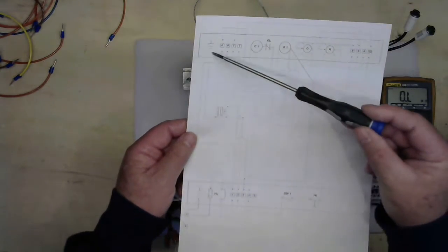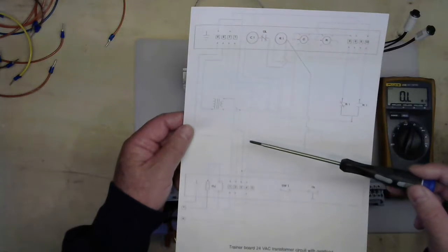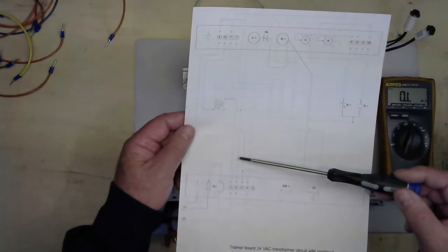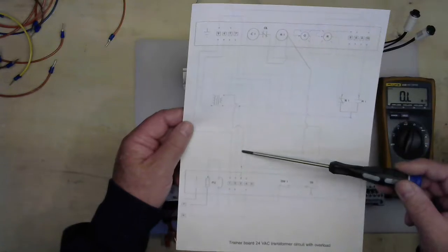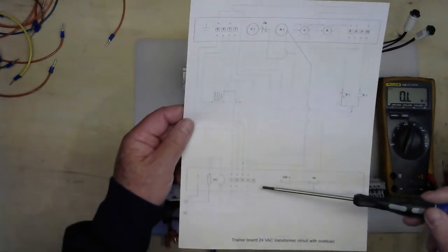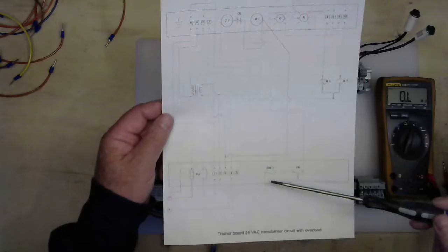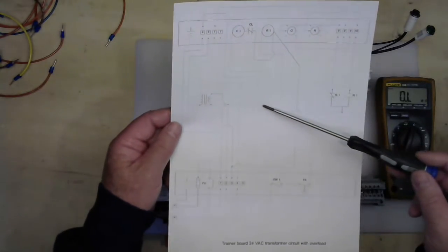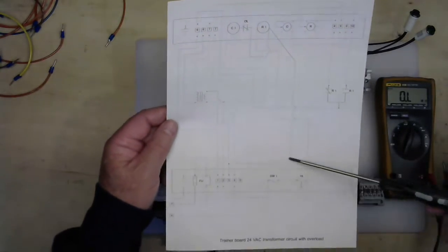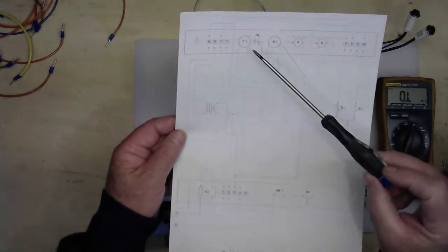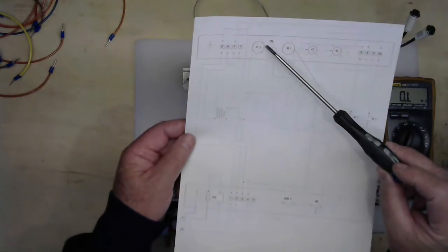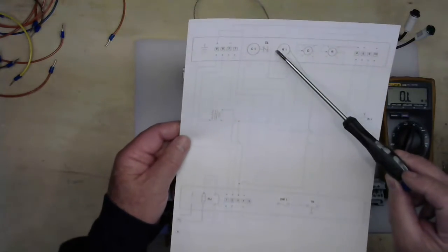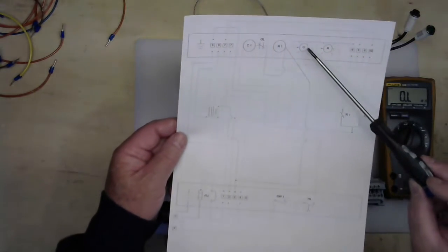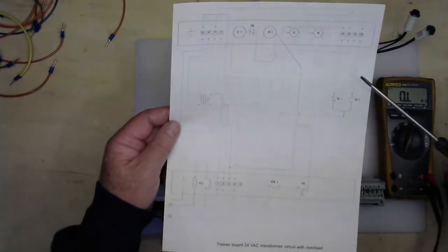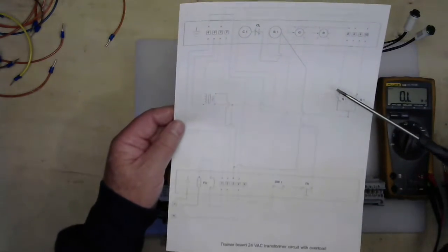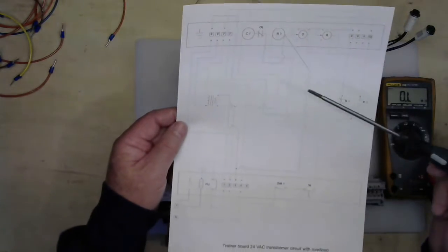The blue lines are representing 120 volts. The orange/red lines and green lines are representing my 24 volts, positive, negative. My reddish orange lines here are my power, and my green is my neutral. I'm using a contactor that's 24 volts AC, a relay that's 24 volts AC, two indicator lights at 120 volts that would be powered up by our R1 relay up here.